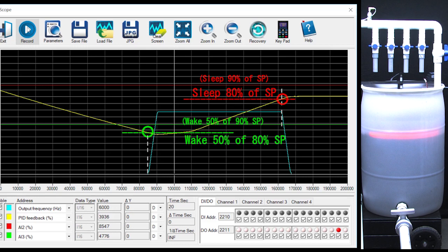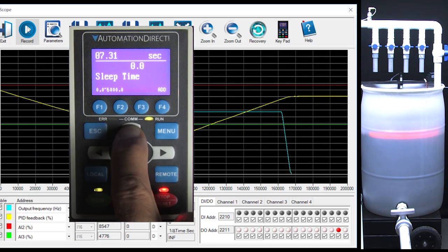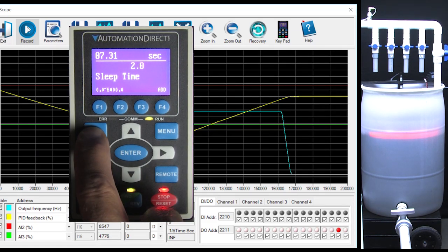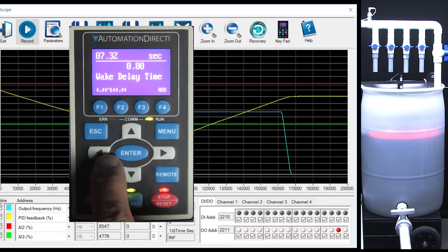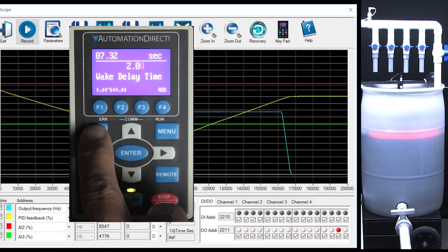You can also delay wake and sleep to make sure the process variable is really past the level before sleep acts. Let's add a 2 second delay to the sleep and let's add a 2 second delay to wake up.